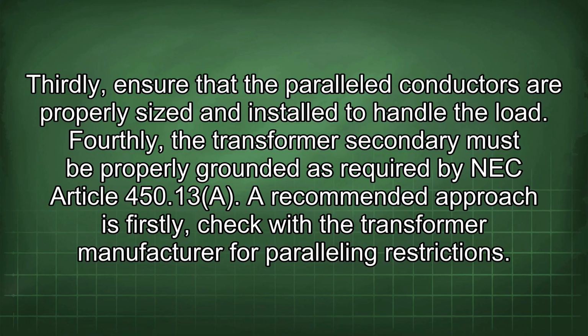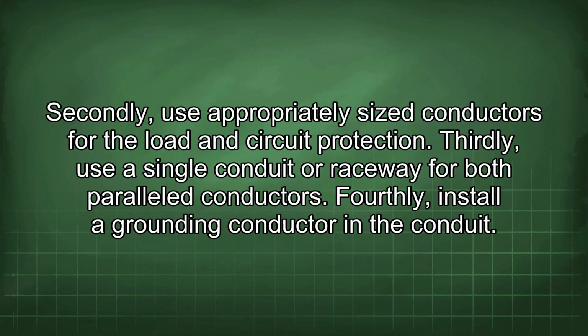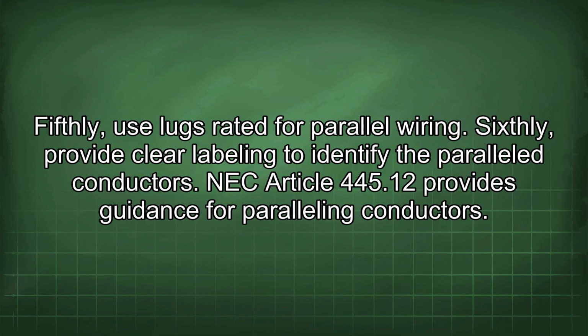450.13a. A recommended approach is firstly check with the transformer manufacturer for paralleling restrictions. Secondly, use appropriately sized conductors for the load and circuit protection. Thirdly, use a single conduit or raceway for both paralleled conductors. Fourthly, install a grounding conductor in the conduit. Fifthly, use lugs rated for parallel wiring. Sixthly, provide clear labeling to identify the paralleled conductors.